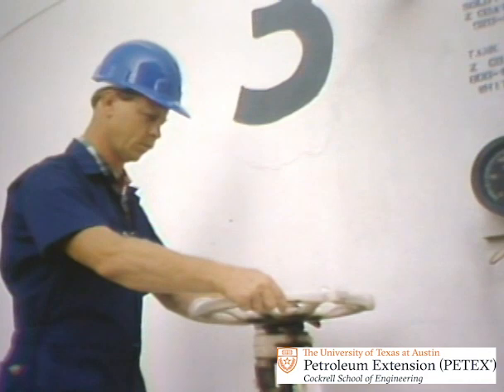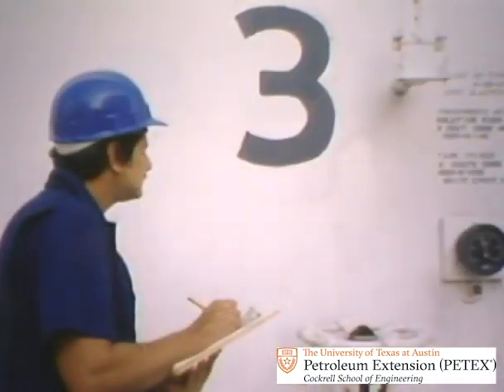All inlets and outlets on the tank must be closed. Normally, if the tank contains a liquid while being strapped, none can be moved in or out. A number should be stenciled on the tank for identification purposes. Also, they find the builder's monogram on the tank. This gives such information as the name of the manufacturer, its erection date, and nominal diameter, height, and capacity. This data gives the crew basic measurements they need to start strapping.